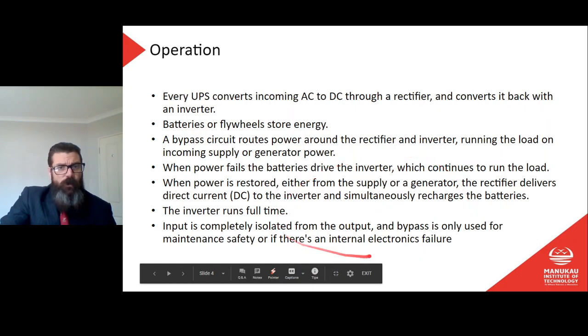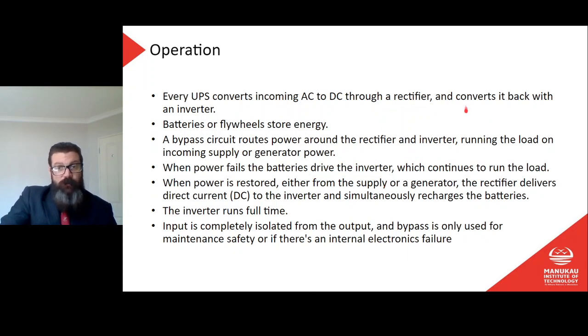Perfect. Every UPS converts incoming AC to DC through a rectifier and converts it back with an inverter. So it's converting the AC to DC to power the battery, to charge the battery, and then converting it back with an inverter because when we go into battery power, we need to change that battery power DC back to AC, put out to our machine.